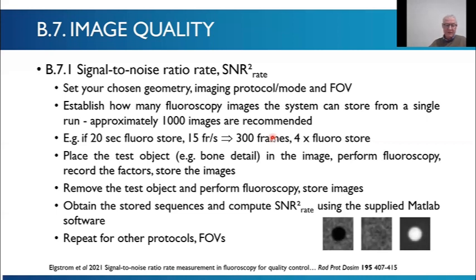You need about 1,000 images, so if you can do a 20-second fluoro store, 15 frames a second fluoro will give you 300 frames. You need to do 4 fluoro store sessions to get the images that you need. And you need to do that for signal present and signal absent. So you put your test object in, for example, a bone detail like this, perform fluoroscopy, record the factors, store the images, and then remove the test object. Again, perform fluoroscopy, store the images, take the images from the system, and then calculate using the supplied MATLAB software, and then calculate your signal to noise ratio rate.